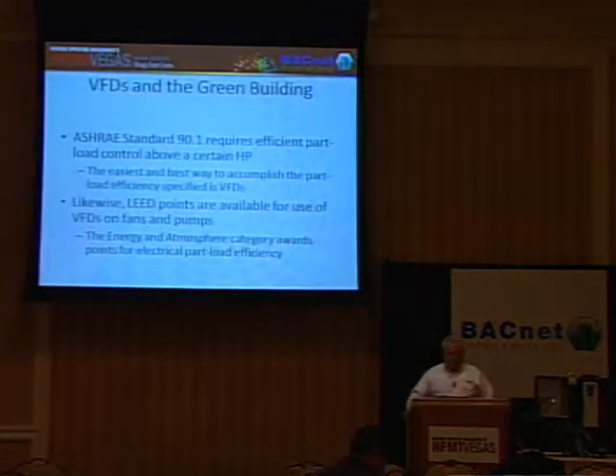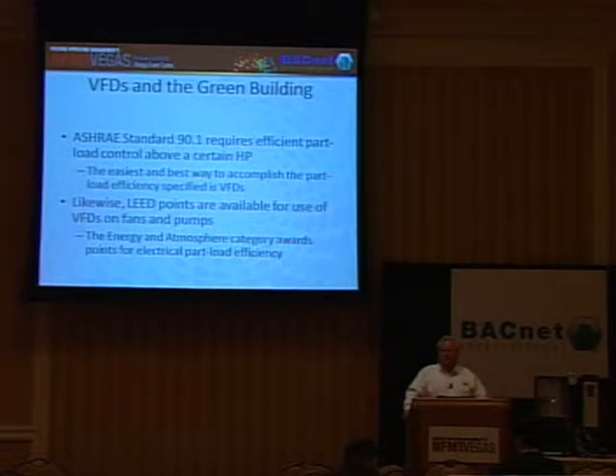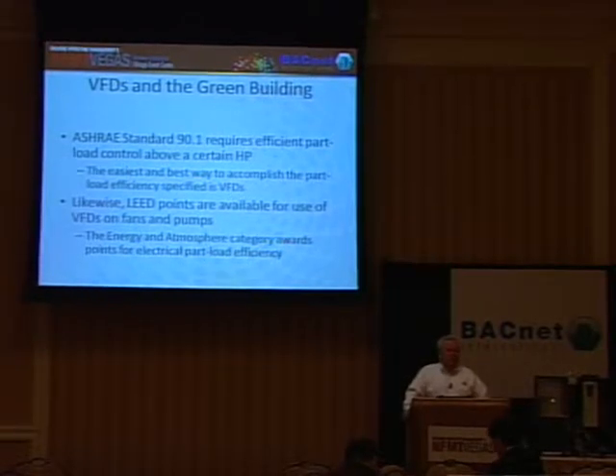VFDs are everywhere in buildings nowadays, whether it's commercial, industrial, or institutional — and that's for several reasons. VFDs used on centrifugal fans and pumps conserve a tremendous amount of energy. Most people know about the affinity laws where horsepower drops as the cube of the speed on a centrifugal fan or pump. So at 50% speed, you only need 12.5% power.